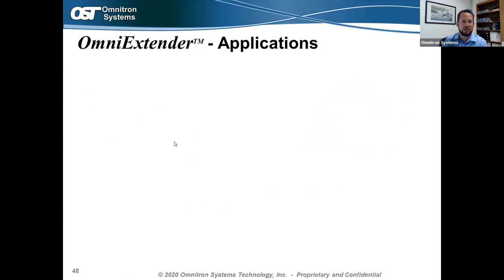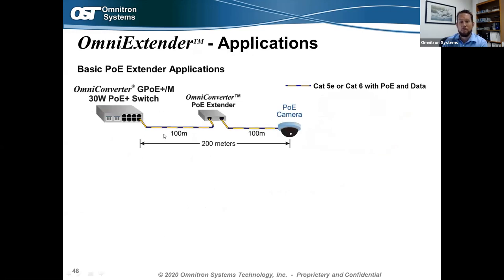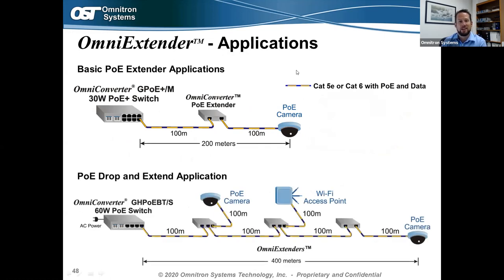Common PoE extender applications: whenever you need to connect a device beyond 100 meters, you can use Omni Converter PoE extenders. Coming out of a 30W switch, it powers the PoE extender with PoE — no local outlet needed — and from there sends PoE up to another 100 meters to a PoE camera over Cat5/Cat6 cabling. The drop-and-extend application is also great: running PoE up to 400 meters from the initial PoE power source by using multiple-port extenders to drop off PoE to a camera or Wi-Fi access point and extend another 100 meters to the next extender.